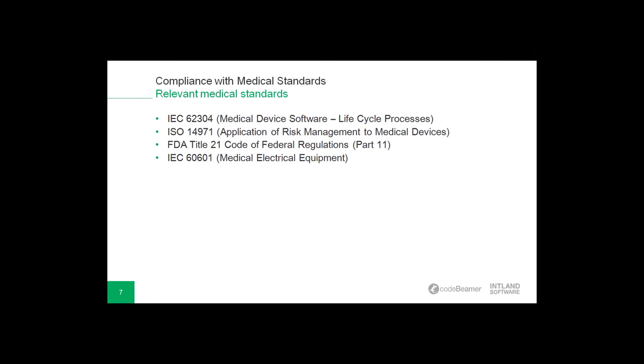On the other hand, the U.S. Food and Drug Administration provides a variety of regulations and standards. Among the most widely applied of these is the CFR Part 11, which covers electronic records and electronic signatures used in medical device development. More specifically, Part 11 regulates the requirements based on which electronic records or electronic signatures are considered reliable and equivalent to handwritten signatures. It applies to the management of controls, audit trails, system validation, documentation, and electronic signatures of the electronic data that is used to prove compliance with other FDA regulations as well.